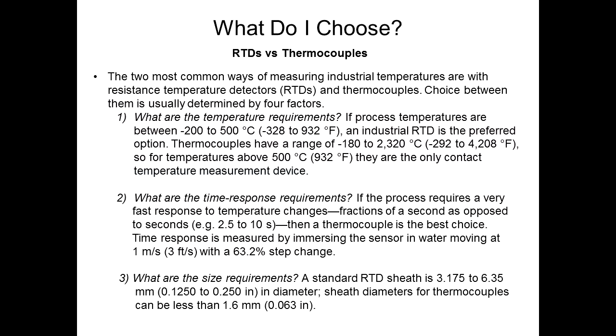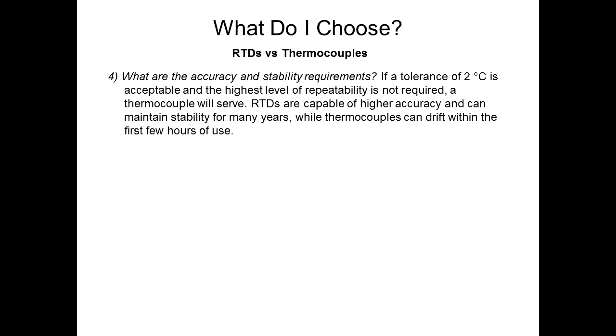Size requirements: RTD sheath is 3.17 to 6.35 millimeters, 1/8 inch up to 1/4 inch diameter. That's about the smallest we can do with an RTD. You can't get a chip any smaller that will go down in it. With thermocouples, you can get thermocouple wire as fine as a human hair, so you can get very small diameter probes. Accuracy and stability requirements: if a tolerance of 2 degrees C is acceptable, and the highest level of repeatability is not required, a thermocouple will serve. RTDs are capable of higher accuracy and can maintain stability for many years, while thermocouples will drift fairly quickly depending on how many cycles they're going through and the temperatures they're exposed to.